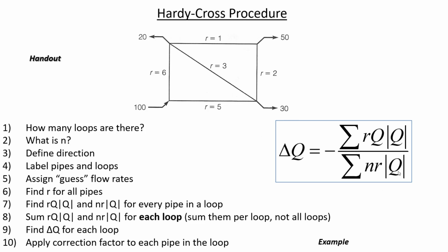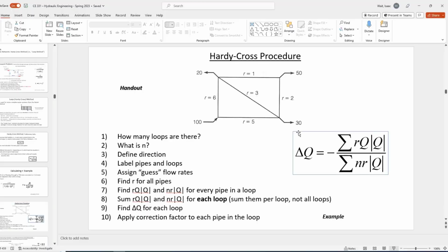So this formula is balancing out the friction losses. Remember how I said that each route in the network has to have the same amount of head loss regardless of which way the water goes through there? We want to find out what flow rate makes it so that all the head loss amounts are the same. Because it's been set up that way, this formula calculates that and adjusts based on the deviation from what flow rate would give you the appropriate amount of head loss that causes the same head loss through every route. So let me show you how this works.